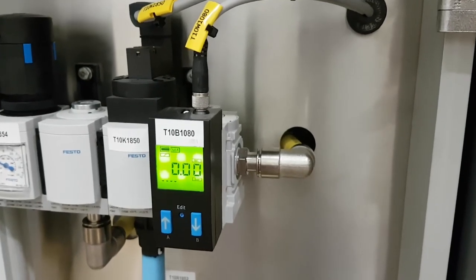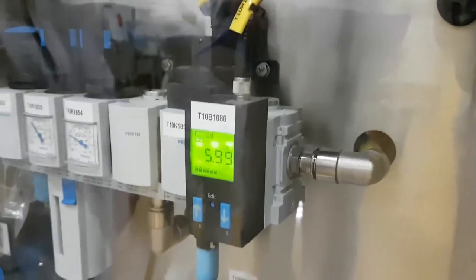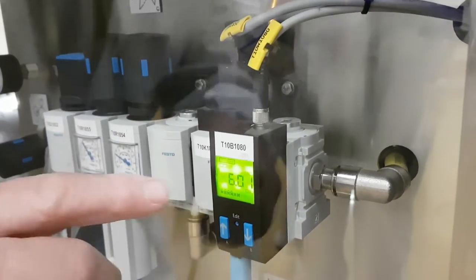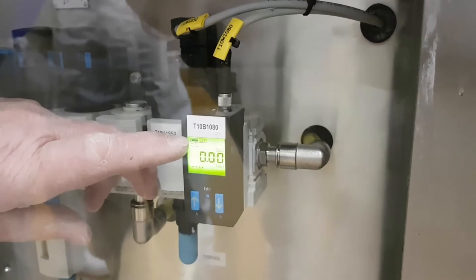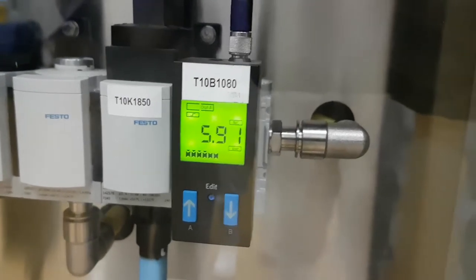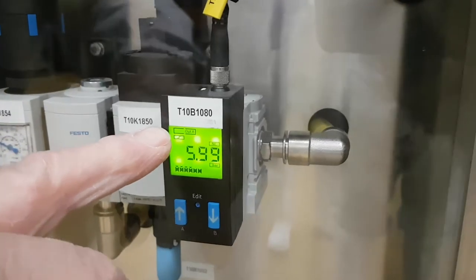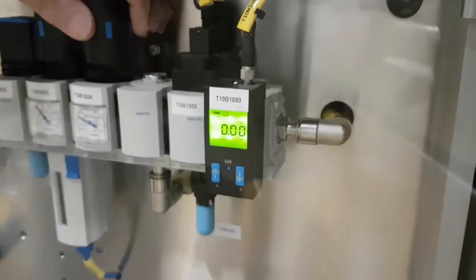So what was your switch point? 4.5. So if you close this now. Reset alarm. Now you have your main pressure. So if you turn this down here to below 4.5, then you will see that this will go and put out. Here. This is off. Now it's off. Here. Now this is on. The black line is gone away. If you turn this down.